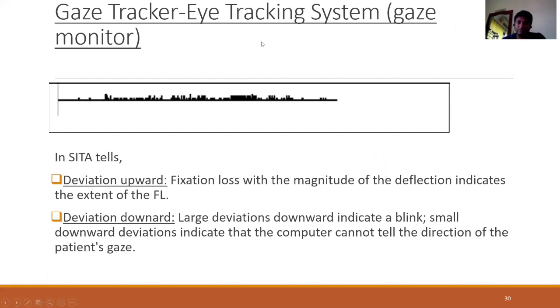The gaze tracker is an optional system not available in all perimeters. It is used to check for fixation losses using the SITA strategy. An upward deviation indicates a fixation loss, with the magnitude of deviation indicating the degree of fixation loss. A large downward deviation indicates a blink, while a small downward deviation indicates the machine could not track the eye. Accuracy is about 1-2 degrees.